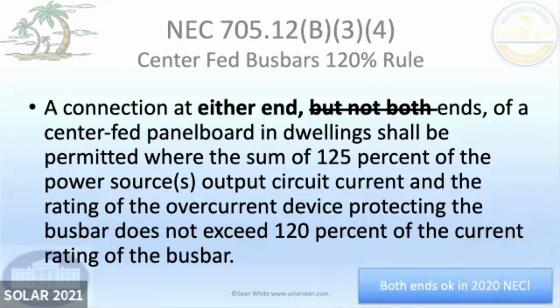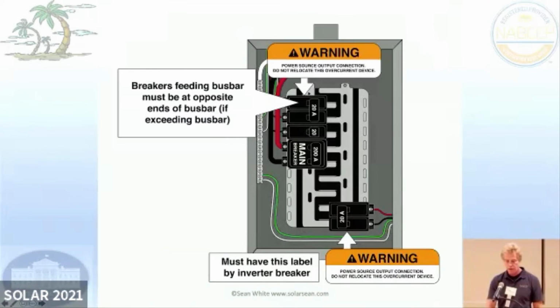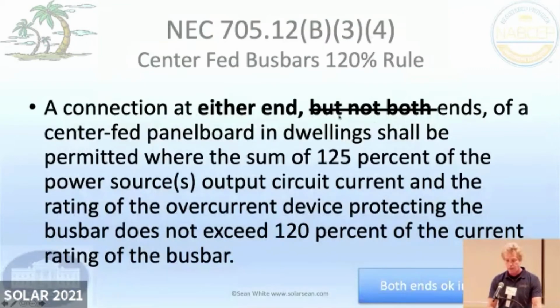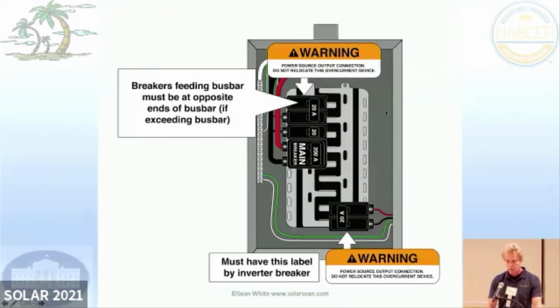And so a lot of times the further west you go, the more oftentimes you have a center-fed bus bar. You've got a main breaker in the middle, and then you can put solar on different sides of that bus bar. So the 2017 NEC said you could pick one side or the other, but not both. The 2020 NEC got rid of the "not both." So if I had the 120% rule and I had a 40 amp allowance, I could put a 20 on each side. If I'm doing the 120% rule, I still need that do not relocate sign.